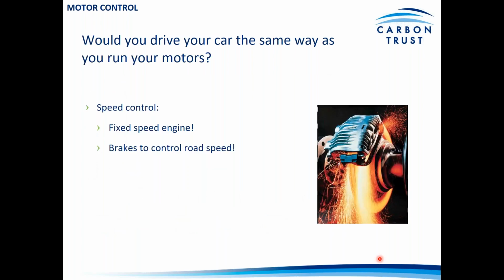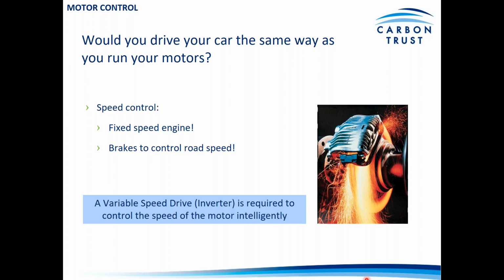So you can see in this example, considering what it'd be like to drive your motor the same way you drive your car. So a fixed speed engine with brakes to control the road speed. As ridiculous as that looks, that is what can happen in some systems, that you have fixed speed motors that are being damped or being controlled in very basic ways to reduce their speed. But ultimately, what you need is a variable speed drive or an inverter system to control the speed of the motor intelligently. We'll probably use the term variable speed drive and inverter interchangeably here, and essentially they are the same thing.